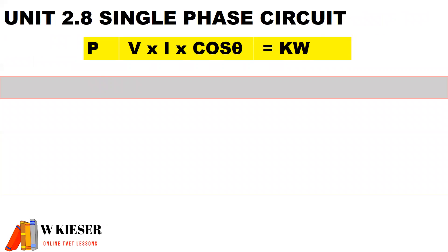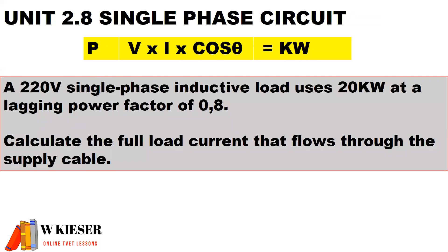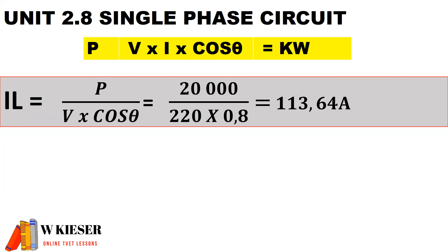Moving on to single-phase circuits: to calculate power, it's V × I × cos θ, and the units are kilowatts. A 220-volt single-phase inductive load uses 20 kilowatts at a lagging power factor of 0.8. Calculate the full load current that flows through the supply cable. The load current is the power divided by the voltage and the power factor: 20,000 watts ÷ (220 × 0.8). Therefore, the load current is 113.64 amps.